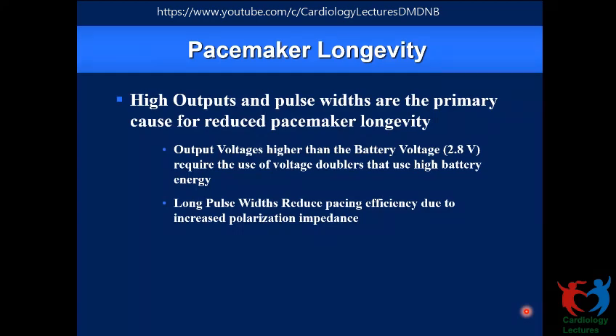Okay, sir. Yes. The important point to remember is, let's say you check the threshold at 1.5 milliseconds and it happens to be 0.5 volts. If you increase the pulse width to 2 milliseconds, it's not going to reduce it further below 0.5 volts. It might at best go to 0.4, not beyond that. So you're not gaining any pacing efficiency, but the energy outgo is significantly higher. So, yeah, that's what it is.